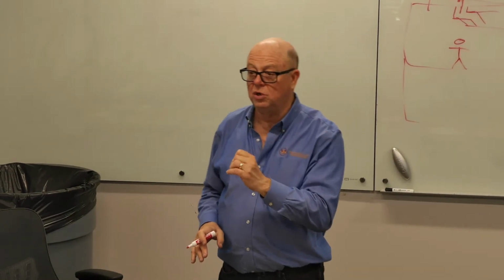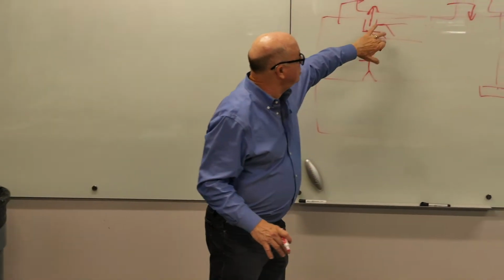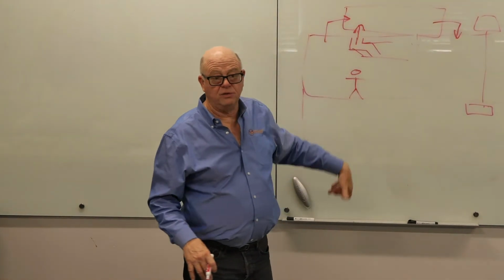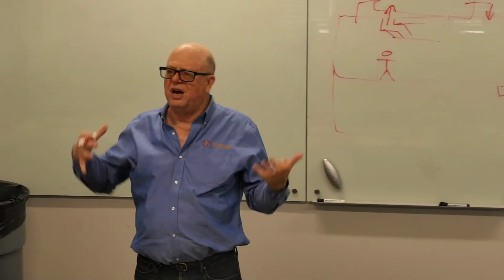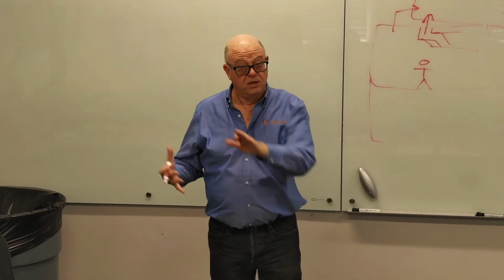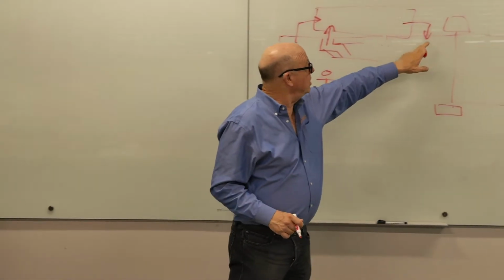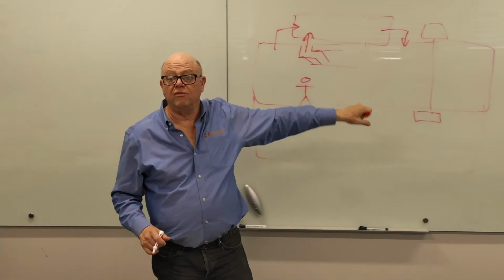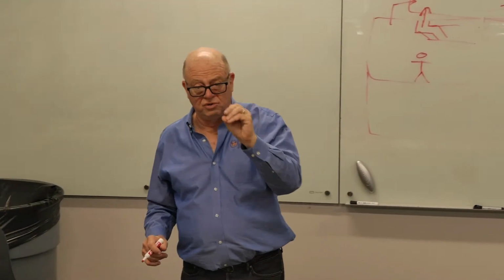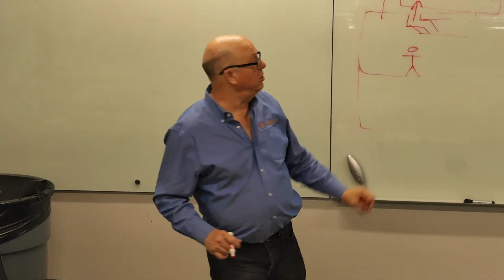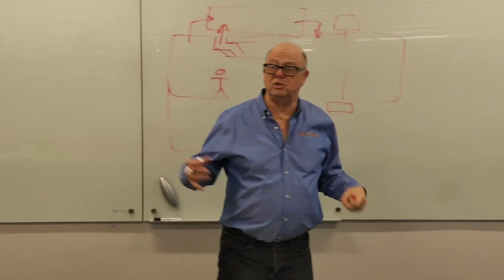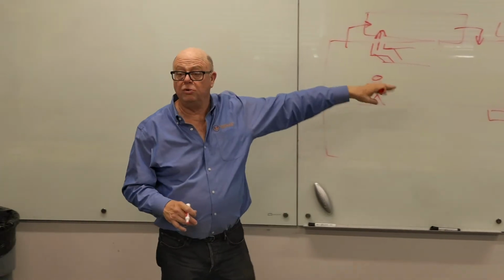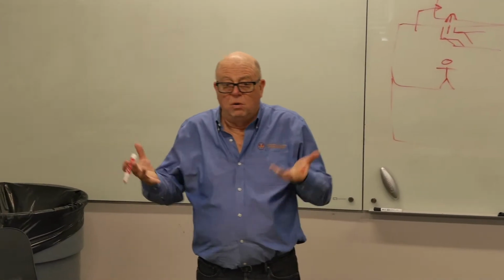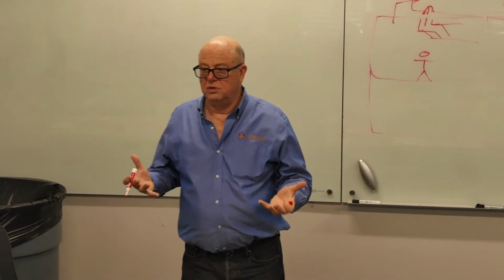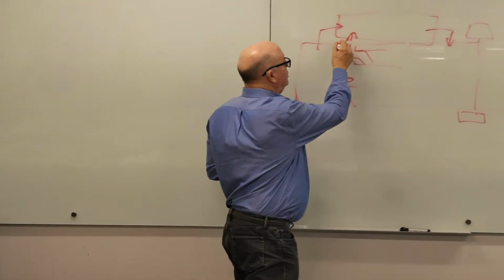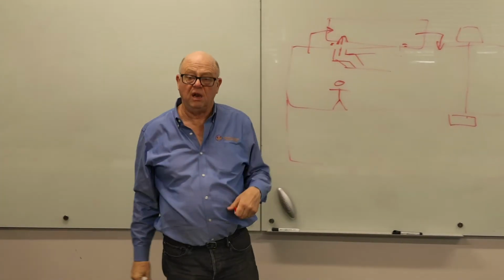There's a lot of things you could do, but the more things you're doing to this, the more cost you're adding to the down shot, and now you're starting to make the side shot maybe a little more competitive. Just think about the side shot. The general contractor is going to have to get the roofer to do a second roof penetration here, and there's going to be some cost associated with that. And you're going to have some outdoor exposed duct, which is going to cost more than whatever you would do down in here, right? So it becomes one of these things. There's also a question of, do I use a spring curb on this unit? That'll help you a little bit.